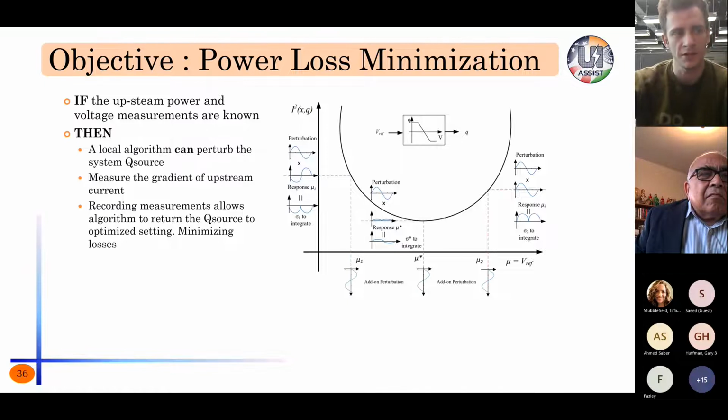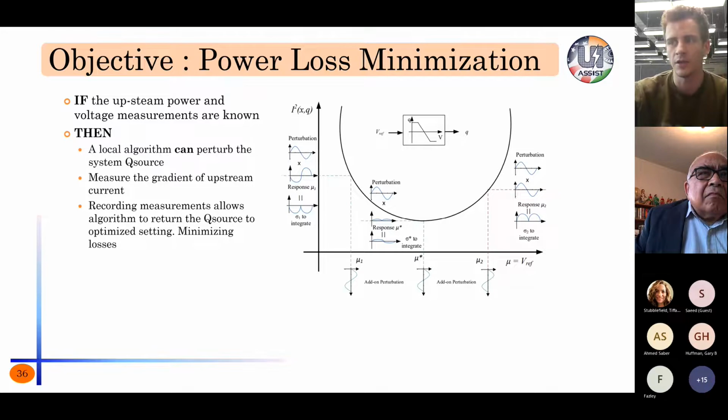And so that goes along well with this idea that it's easily scalable. As you introduce more inverters on your control system via batteries or PV, this scheme just gets more robust, it gets more able to do its job better. And the benefit of it is that since there's no communication between these controllers, it's easy to go beyond smaller areas. You can distribute this with other parties, and they don't have to connect together to grow. So many people can implement this system without having knowledge of each other, which is easy to coordinate. Next slide.